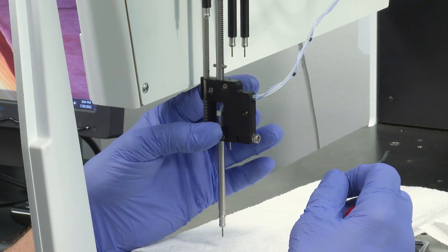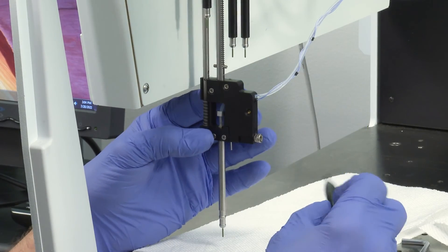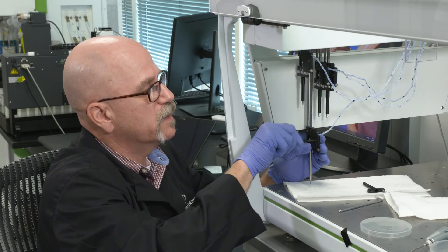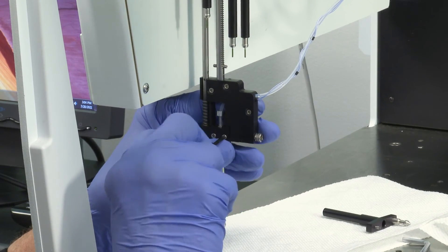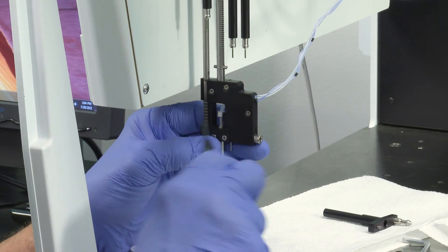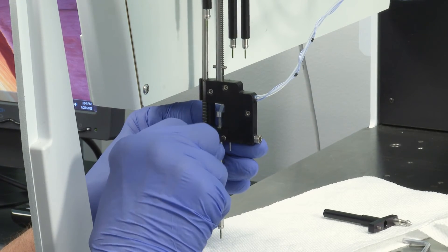If it's to the back or to the front too far, it could interfere and click and cause errors as it contacts the other tip housings. So we put our screws in. We're not going to over-tighten them. Over-tightening them can result in damage to the tip housing cover. We make sure that it was behind the small plate or clamp that holds the VersaTip in place. We snug that up. Snug them all up.